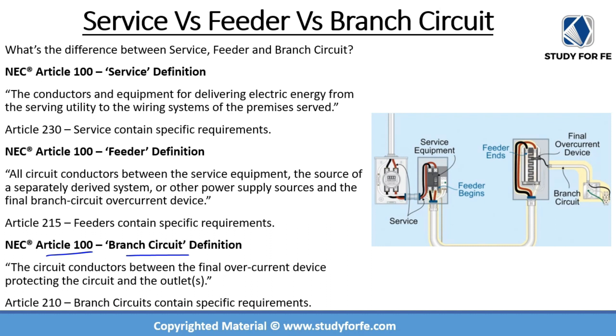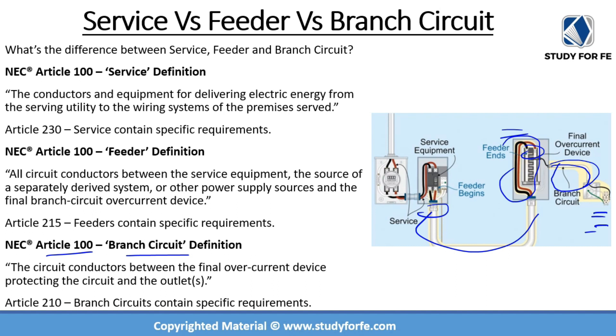The best way to identify a branch circuit is to start from the end load — a receptacle, a lighting fixture, a dishwasher, or an appliance. You start from the end load and make your way up to the distribution panel, which contains overcurrent protective devices for many such loads. The conductor between that panel and your end load is your branch circuit. The conductor on the line side of that panel — whether it's a lighting panel or a switchboard — all the way back to the service equipment classifies as a feeder. And from the line side of the service equipment upstream, that is all service.